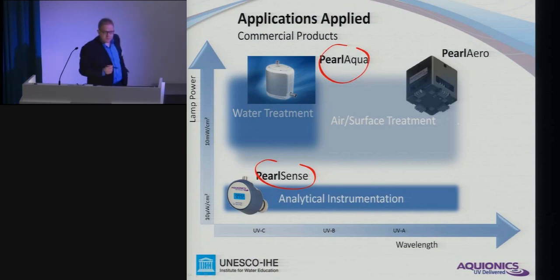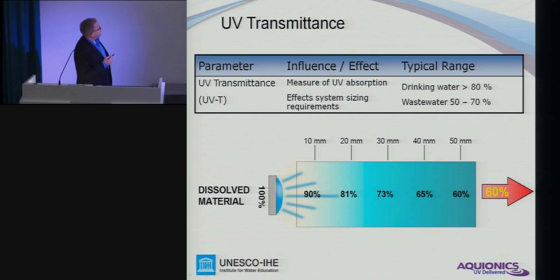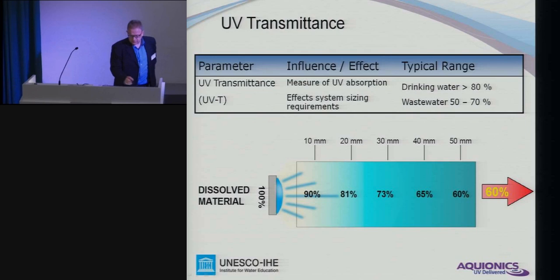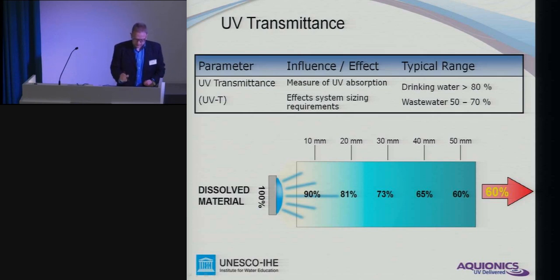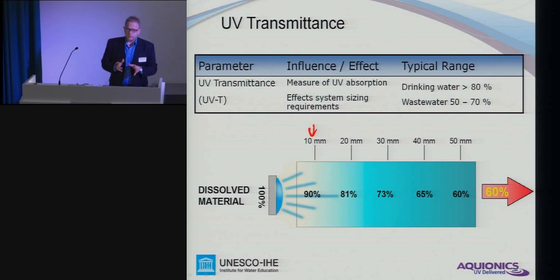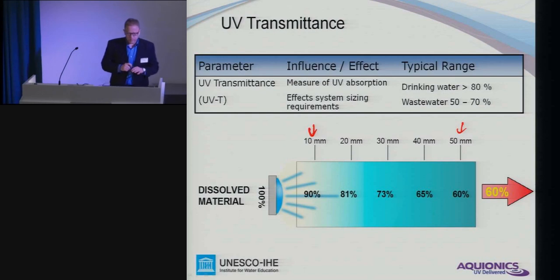UV transmittance was already mentioned this morning. Transmittance at 254 nanometers is basically how much light can travel through — penetrate the water in a layer of one centimeter. If after 10 millimeters we have 90%, then obviously it gets less and less. After 50 millimeters, we only have 60% left. That is important when designing UV disinfection systems, as it determines the distance between the lamps. A clean water system may have a wide distance; a wastewater system with lower quality needs a narrower arrangement of lamps. To select the correct system for a certain application, we need to know the UV transmittance.